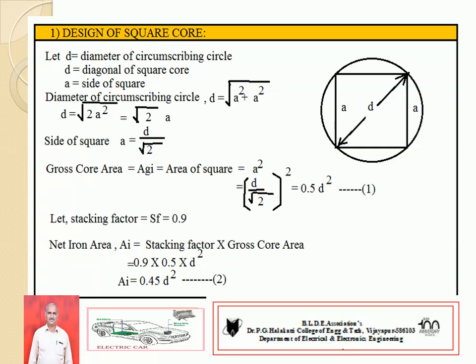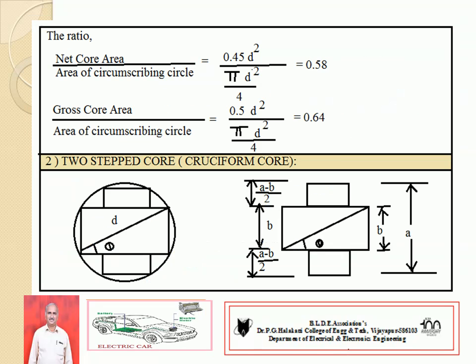The stacking factor is the only difference between gross core area and net iron area. The gross core area is the actual area of the square, and considering the stacking factor, the net iron area is less. Taking the ratio of net core area to area of circumscribing circle: net core area = 0.45 D², area of circumscribing circle = π D² / 4, giving a ratio of 0.58. The ratio of gross core area to area of circumscribing circle is 0.64. This is the beginning of the design.